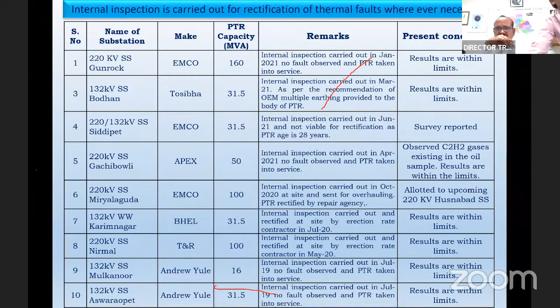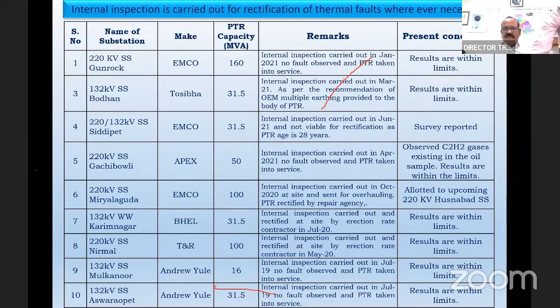Whenever a transformer fails beyond the guarantee period, we are not directly sending it to the repairer. We are opening the transformers at the site itself, and in the last 8 years, we have repaired these transformers at the field itself. Mostly the failures need very minimal repairs at the field. Around 35 transformers have been repaired at field level. We open the transformer in the substation itself, look at the faults, repair it, and put the transformer back into service.